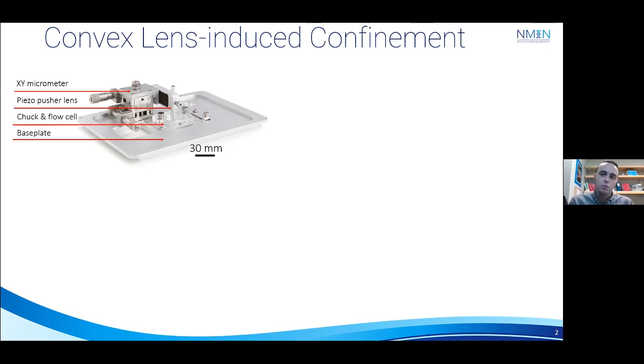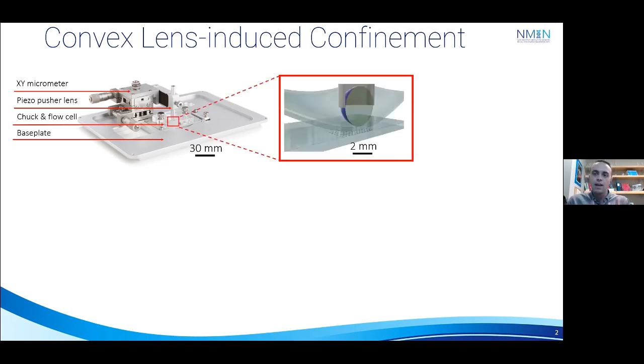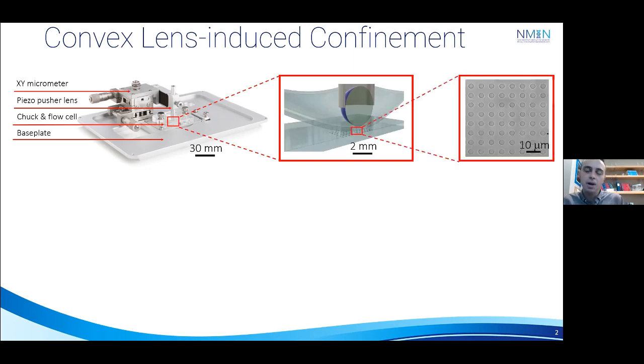And to explain how it works, I'll just zoom in on the two most important components, the flow cell and the pusher lens. And so first we flow our molecules of interest into the flow cell. And then using the pusher lens, we compress the top cover slip into the bottom cover slip. And so if I zoom in further on the bottom cover slip, you'll see that the molecules will become confined within these nanoscopic features etched into the bottom of the flow cell.